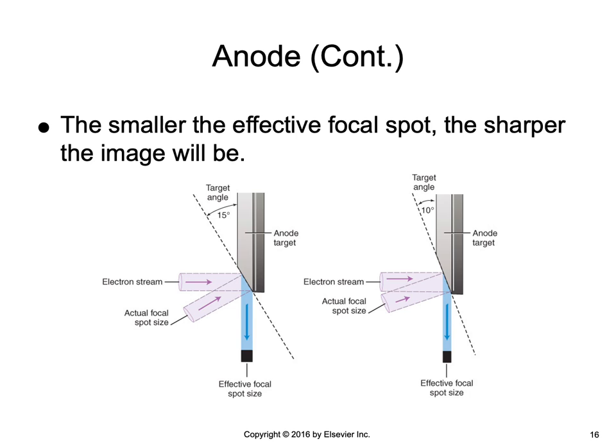This figure illustrates the target angle and line focus principle with two different target angles, showing the effect of target angle on effective focal spot size. You can see that the smaller the target angle, the smaller the effective focal spot size.